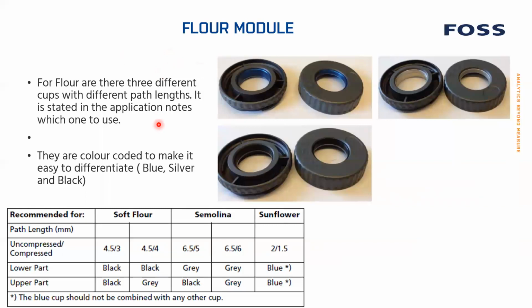There are 3 different cups with different path lengths, so there's different thickness. They are color-coded: blue, silver, and black. And if you look at it, you'll say, no, they're all gray. No, they're not. This is blue, this is silver, and this is black. The plastic around them is gray. And this is then the combination of the type of flour you can use them for. Soft flour is wheat flour. Semolina is normally for pasta. And you have sunflower flour, which is very dark, so it has a very small path length.